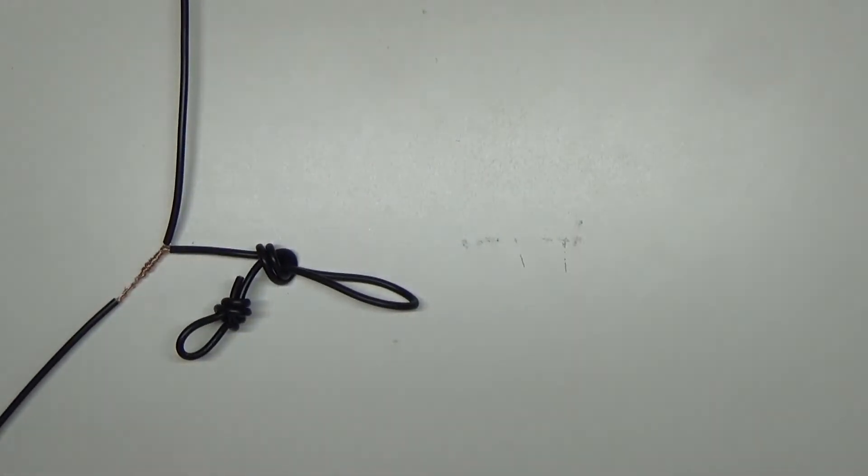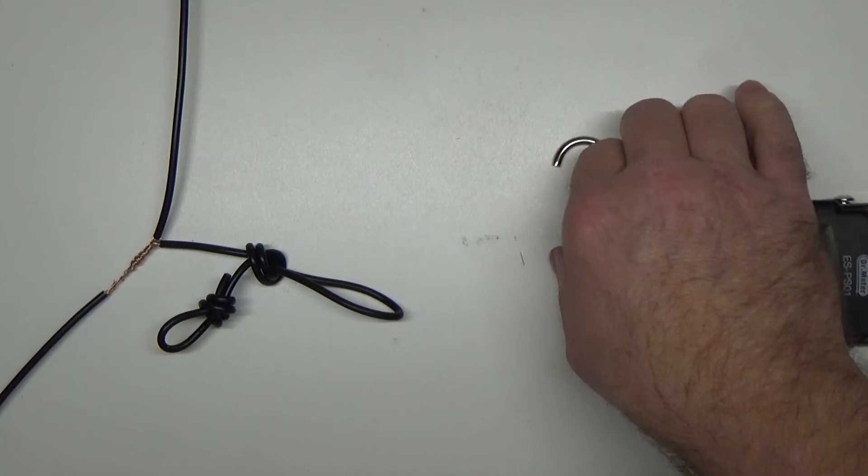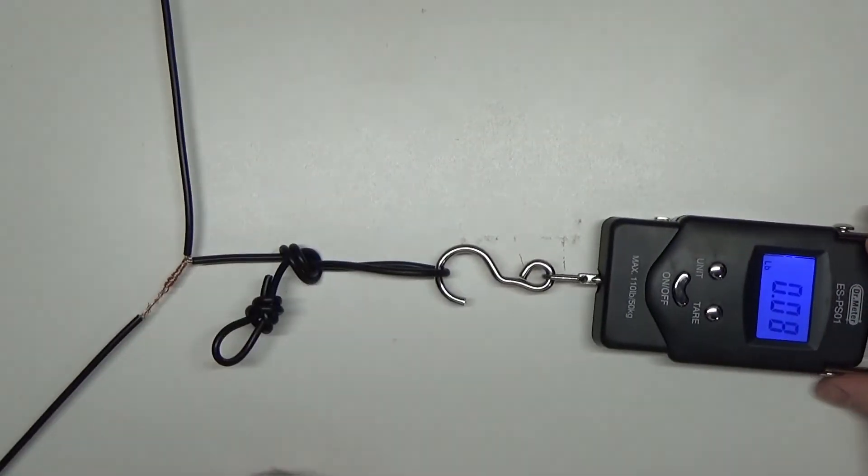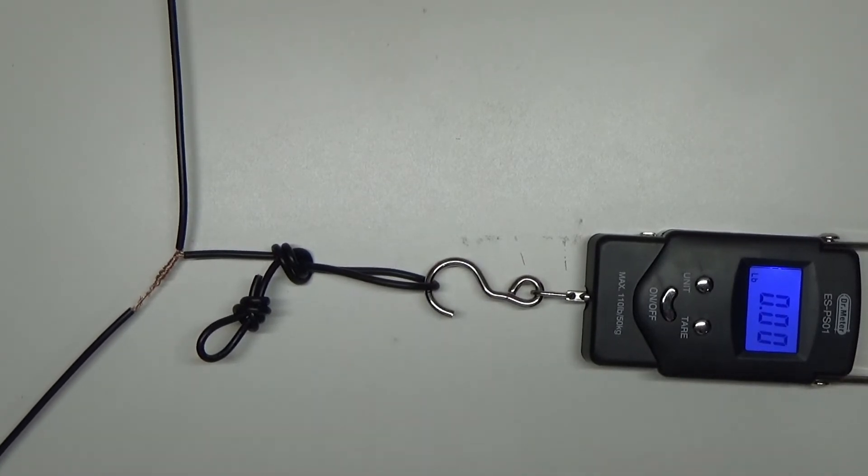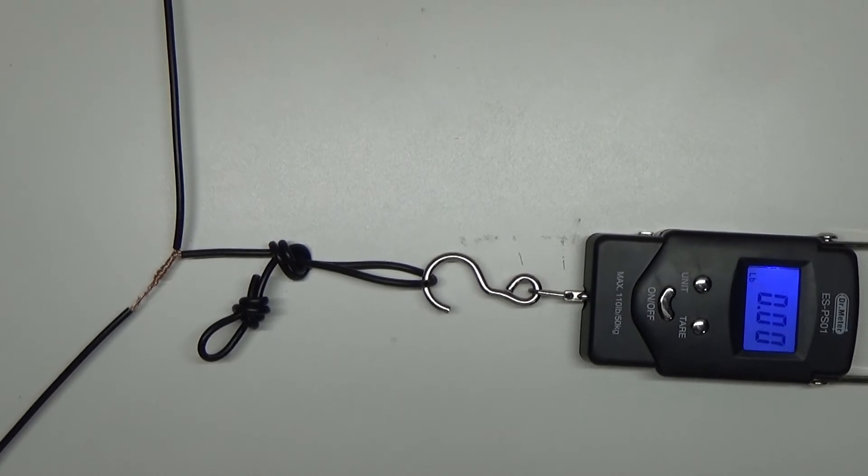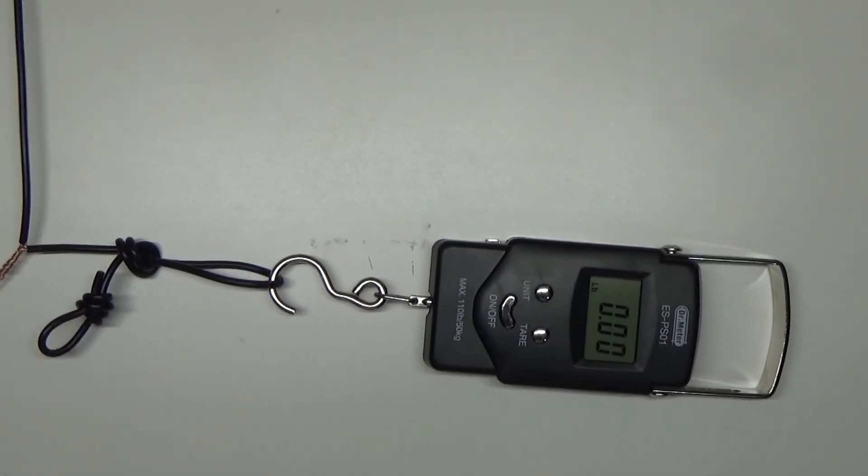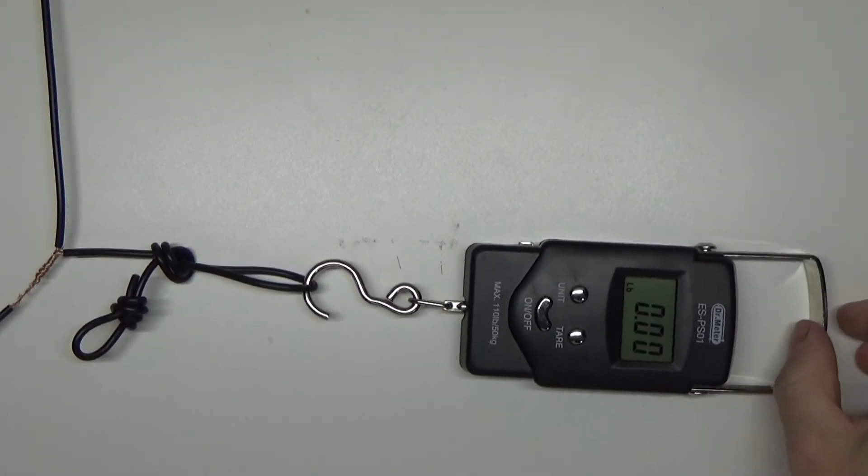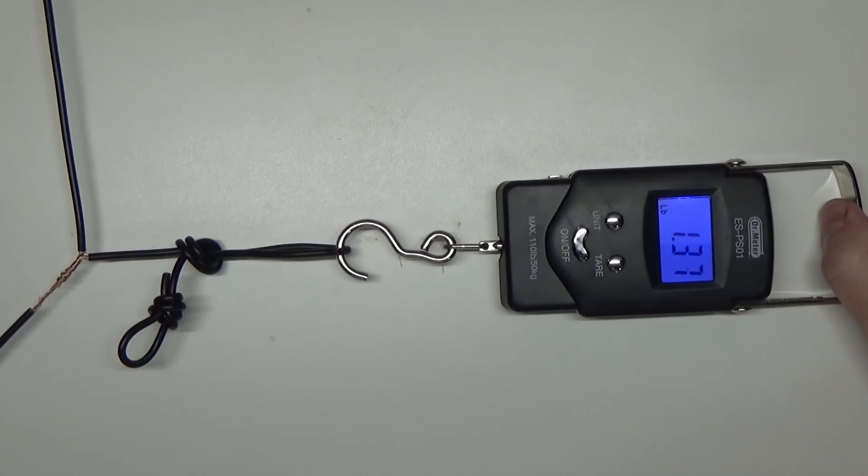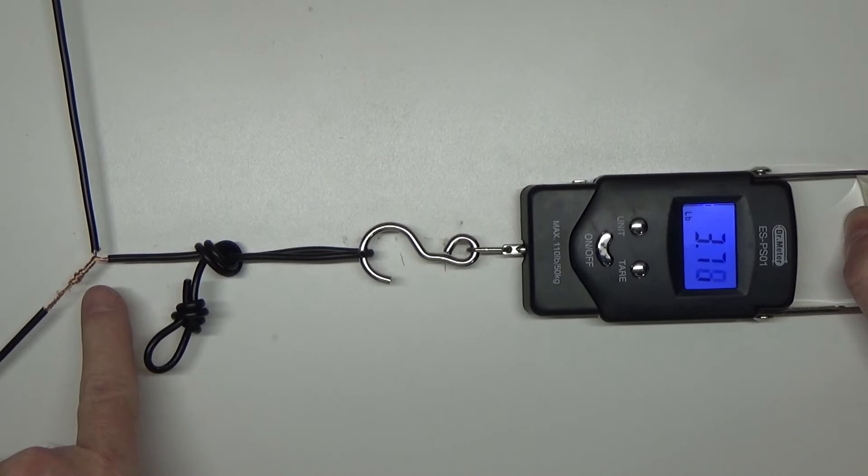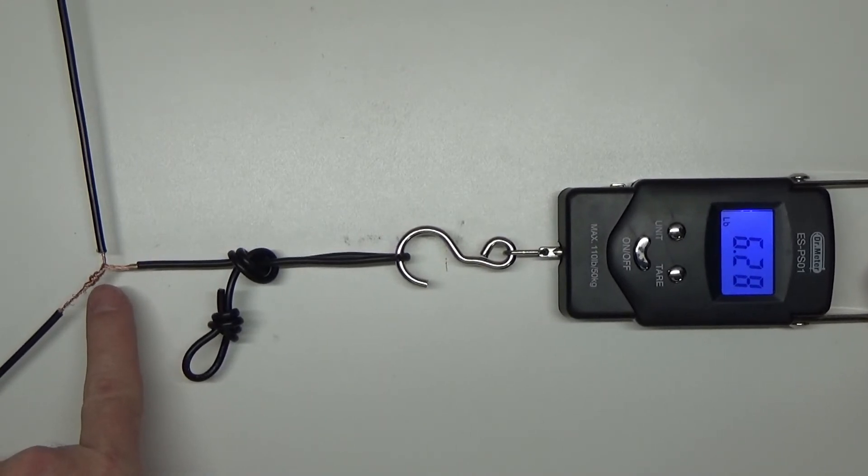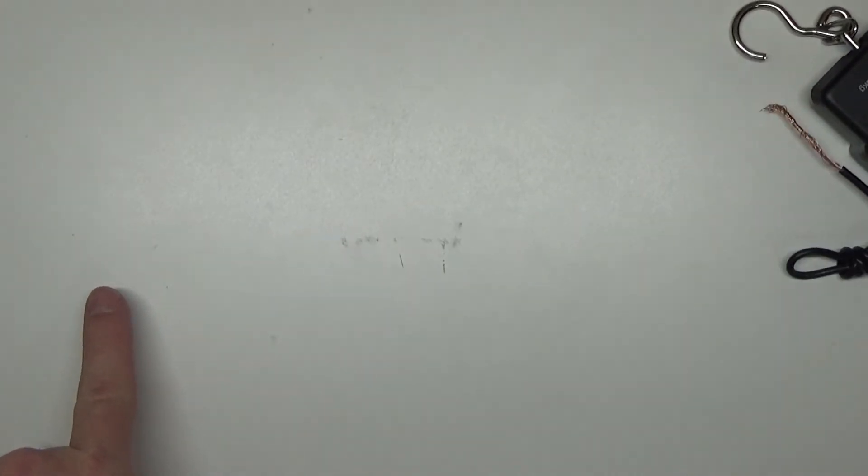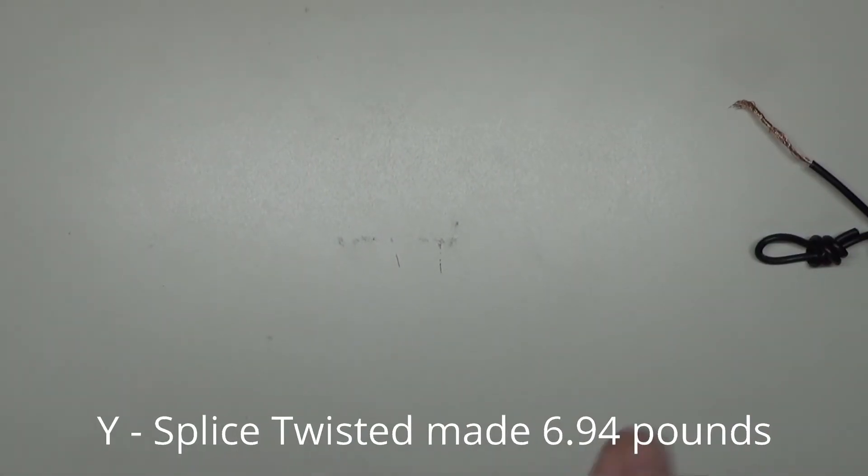There we go, Y splice set up. Take our scale, hook it on here. Here we go, ready? Let's see, let's move our camera a little bit because I want to zoom in a little tighter so you guys can see this and the scale both. All right, ready? Let's do this pull. Look at that, I'm at three pounds to start to unwrap, four pounds, five, six, but it's unwrapping. There you go. So I made it to 6.8 pounds I think, I'll have to look at the video here in a bit to confirm that.